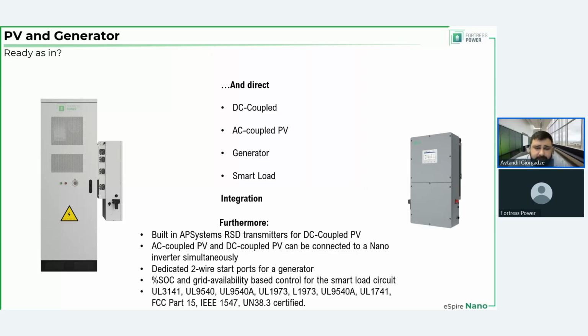Also, this system can be directly connected to DC coupled PV. So you bring the PV strings and you utilize the built-in MPPTs to turn that PV production into useful AC. It can also do AC coupled PV. It can do both at the same time, by the way. It can facilitate a generator integration, and it has a smart load feature. In a sense, you have a controlled backup output for one particular load or load circuit.